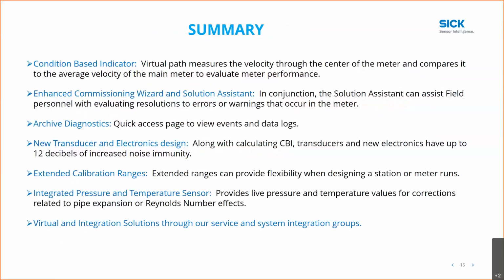So in summary, the condition-based indicator, or CBI, the virtual path, measures the velocity at the center of the meter and compares it to the average velocity of the main meter to evaluate meter performance. Enhanced commissioning wizard and solution assistant: in conjunction, those two features allow the solution assistant to evaluate resolutions to errors or warnings that occur in the meter. The archive diagnostics is a quick access page to view events and data logs and evaluate anything that may have occurred during a specific date span.